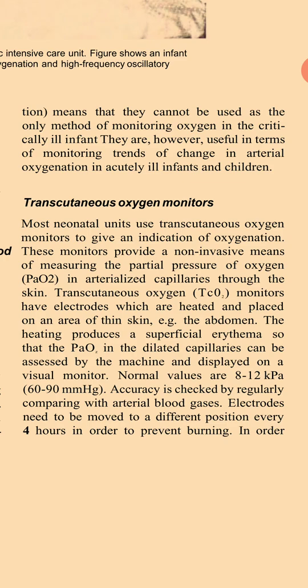Transcutaneous oxygen monitors. Most neonatal units use transcutaneous oxygen monitors to give an indication of oxygenation. These monitors provide a non-invasive means of measuring the partial pressure of oxygen in arterialized capillaries through the skin. Transcutaneous oxygen monitors have electrodes which are heated and placed on an area of thin skin, for example the abdomen. The heating produces a superficial erythema so that the PO2 in the dilated capillaries can be assessed by the machine and placed on a visual monitor. Normal values are 8 to 12 kPa, 60 to 90 mmHg.